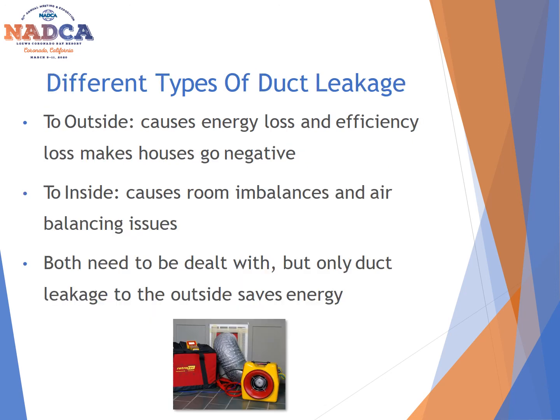When it comes to duct leakage, there are a couple of things that can happen. You can be losing air to the outside of the duct system, to the building envelope, which means you may be exhausting into the attic or into a crawl space. When this happens, especially on the supply side, you actually put the house under negative pressure, which means you're now sucking in dust and debris from outside, from areas you don't want to be sucking air from, in order to create a balance in the system.